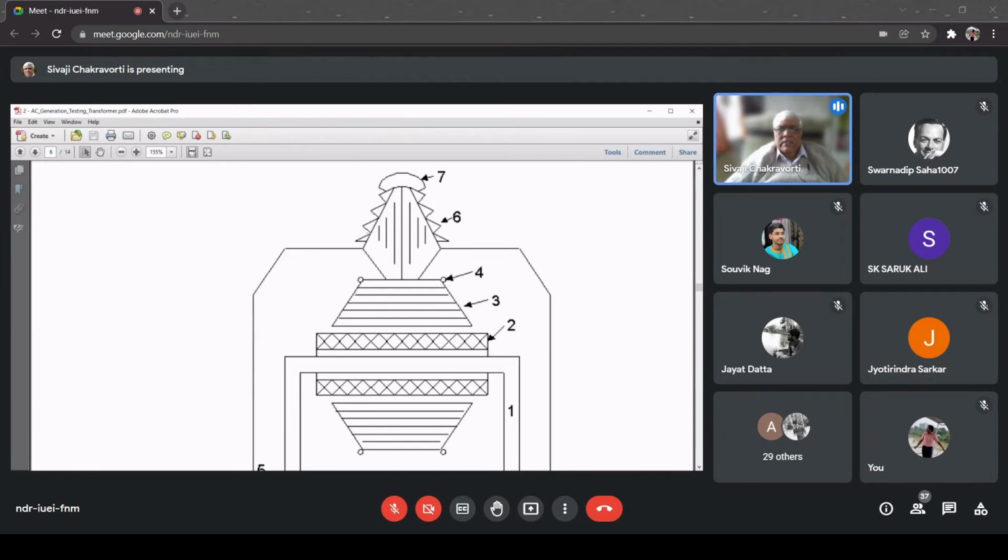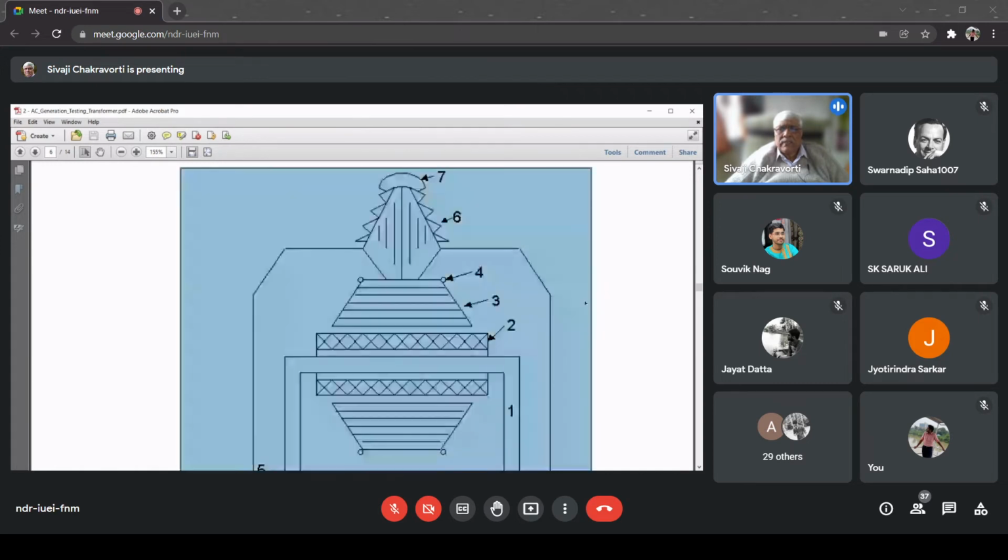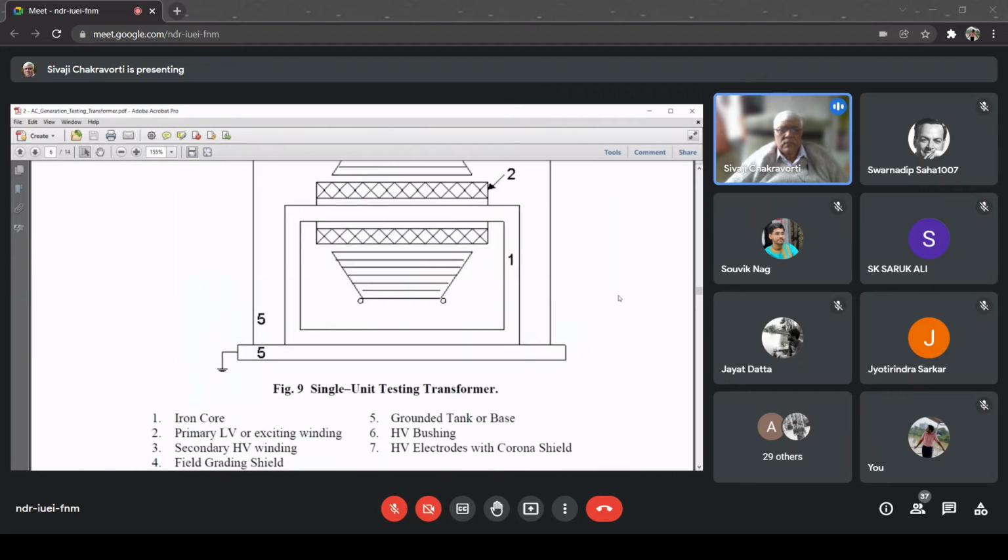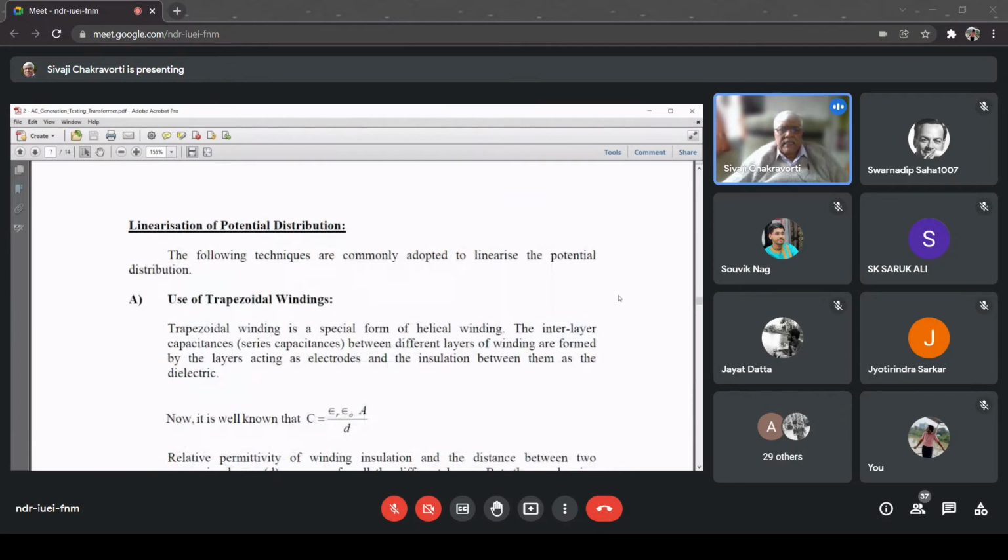And in all such applications where a high voltage conductor has to pass through the earth body, you have to use bushings. You cannot use insulators. So for example, if some high voltage terminal is inside the lab, then the lab has a wall and some outside object has to be tested. So the connection has to be taken through the wall to outside. There you can't use an insulator. You have to use a bushing. So in this way, these bushings are used in our high voltage cases.